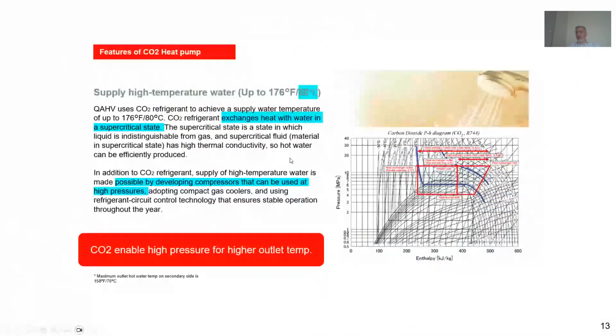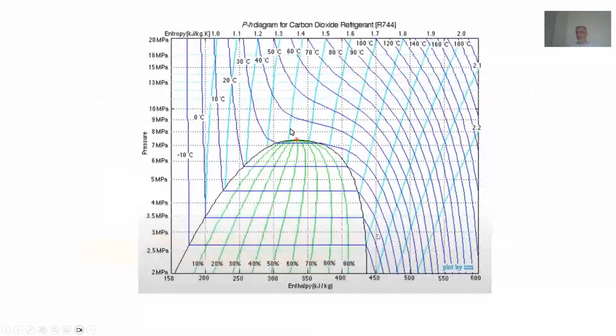Let's go a little bit into how CO2 works in this application. CO2 works at a higher temperature and higher pressure level, so it can provide up to 80 degrees centigrade hot water for domestic use. Let's move to a typical PH diagram, where the compressor does work and increases the pressure and temperature. In the heat exchanger, it gives its energy to the water. Let's say the water comes in at 55 degrees centigrade, it stops here.